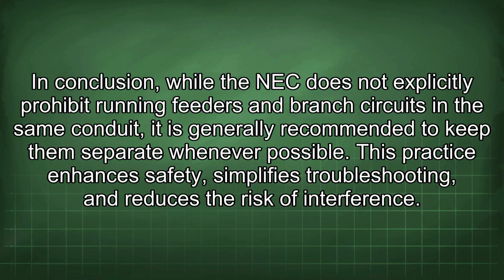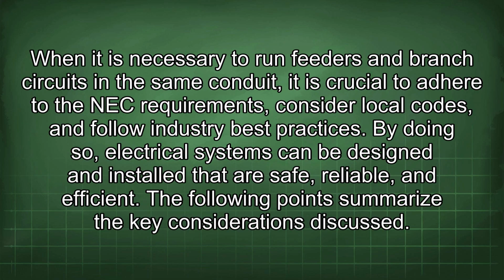In conclusion, while the NEC does not explicitly prohibit running feeders and branch circuits in the same conduit, it is generally recommended to keep them separate whenever possible. This practice enhances safety, simplifies troubleshooting, and reduces the risk of interference. When it is necessary to run feeders and branch circuits in the same conduit, it is crucial to adhere to the NEC requirements, consider local codes, and follow industry best practices. By doing so, electrical systems can be designed and installed that are safe, reliable, and efficient.